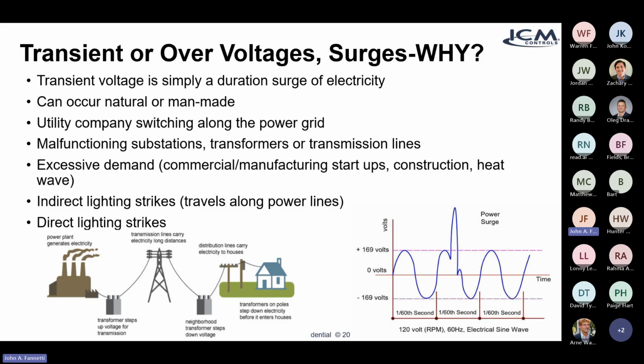Indirect and direct lightning strikes can cause surges to happen. As we can see, a surge is that spike that you see. You got your normal voltage, and then all of a sudden you get this very fast-acting transient surge. So you need something to protect not only against those transient surges, but you also have problems with the voltage. In three-phase, for example, you have three different phases that have to be always maintained. And things can go on where you could lose a phase, you could be having unbalance, which we'll get into very shortly.